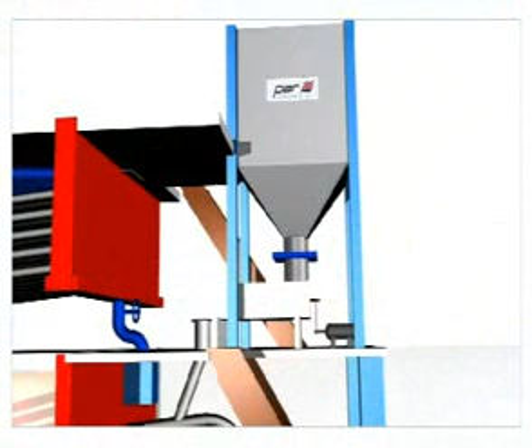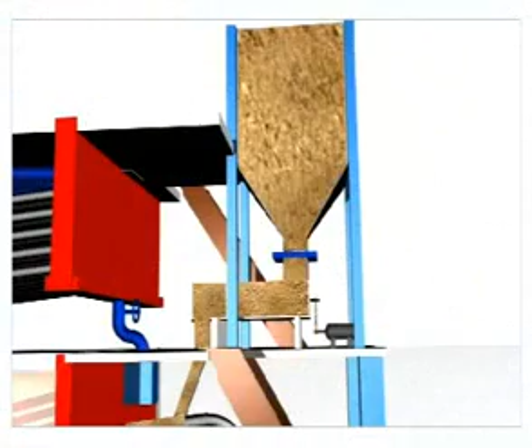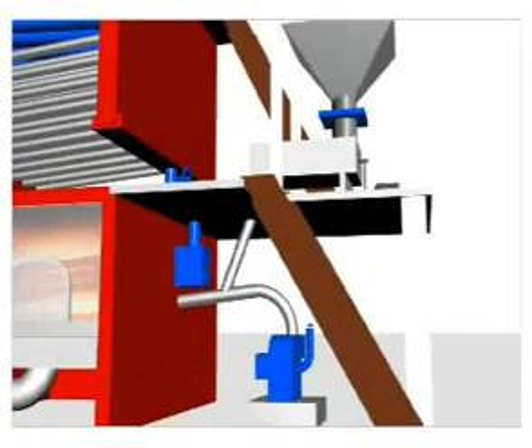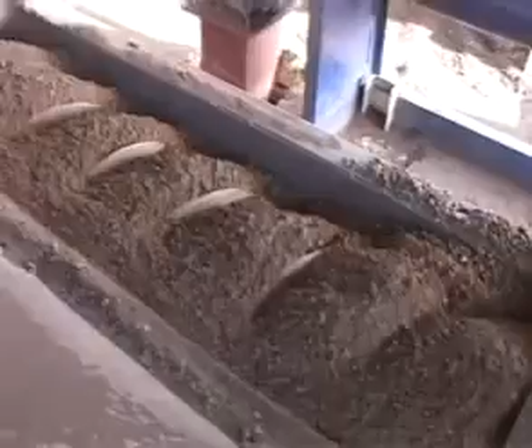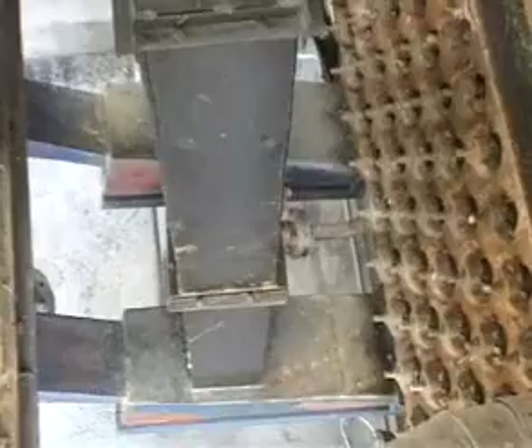Injection of fuel, that is, fuel feeding. Fuel in the hopper is injected to the FBC furnace bed, below the in-bed cooling tubes, with the assistance of secondary fuel feed FD fan. Fuel like coal, lignite and agro waste can be injected to the FBC furnace. Rate of fuel feeding is controlled by VFD of screw feeder. Fuel is fed in the furnace bed.